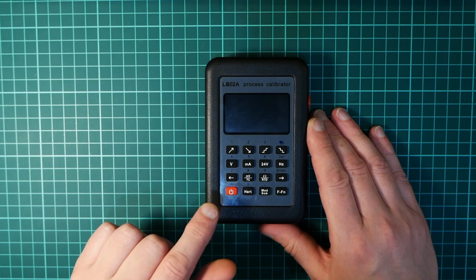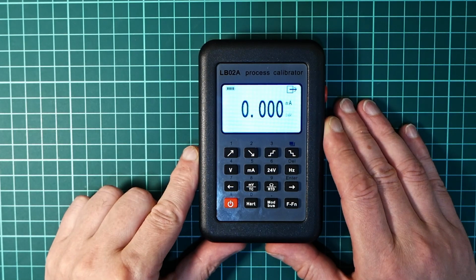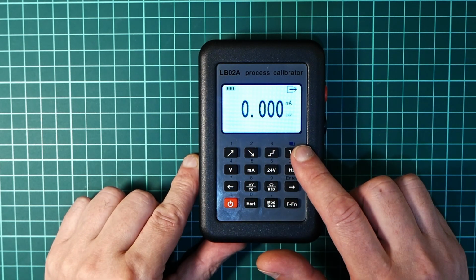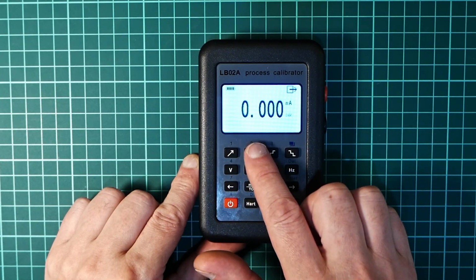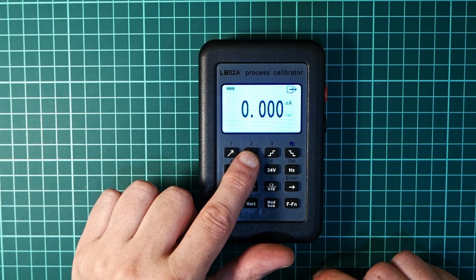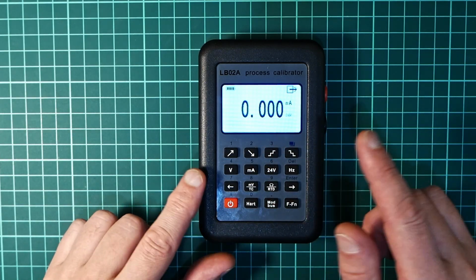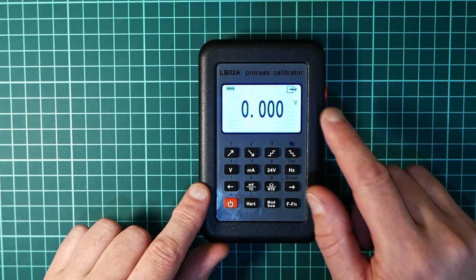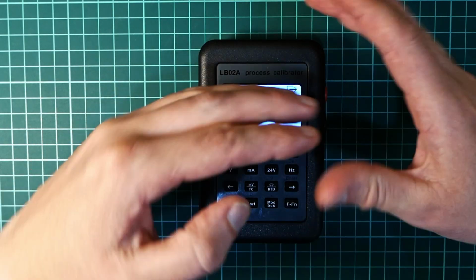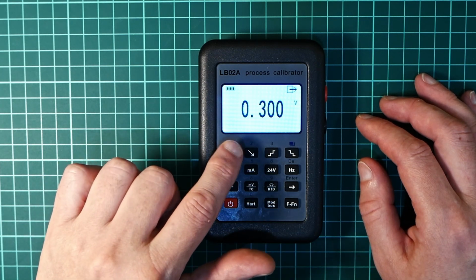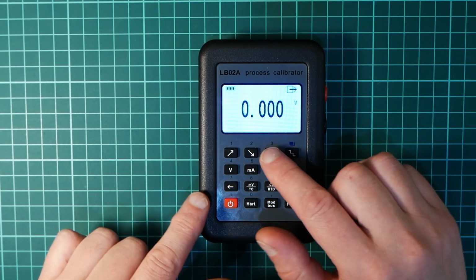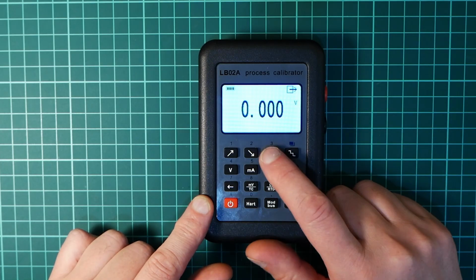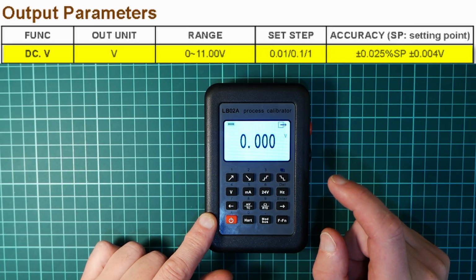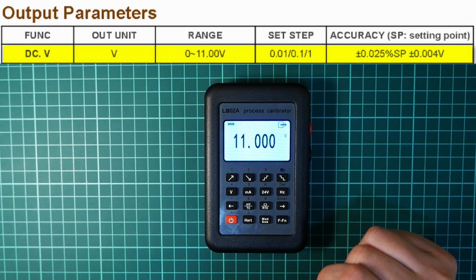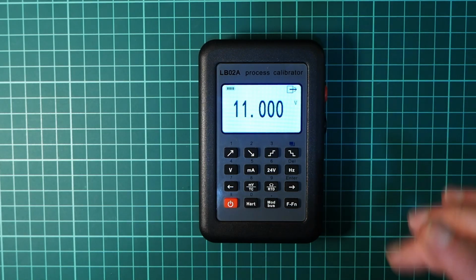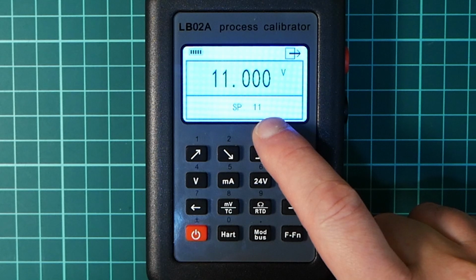So to turn it on, we press the power on push button, and it has these adjustment push buttons on top. These two, up and down, are kind of fine tuning. These are more rough adjustment. If we select voltage mode, right now it's in output mode, okay, arrow like that. We can go up by 100 millivolts, and with these rough adjustment push buttons we can go 1 volt up, 1 volt down. We can go up to a maximum of 11 volts. Now if you want a very specific voltage, you can press the function button, and here is set point value.